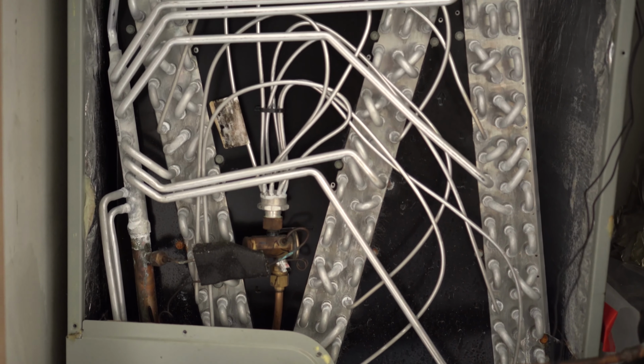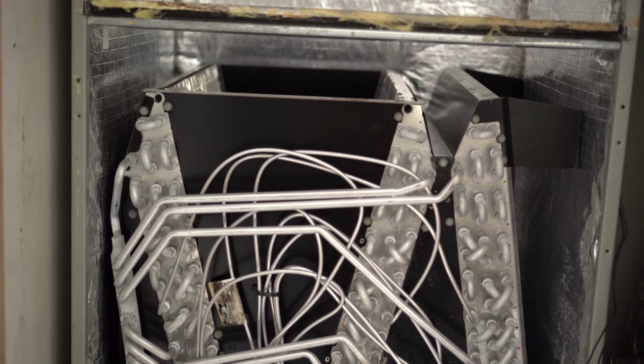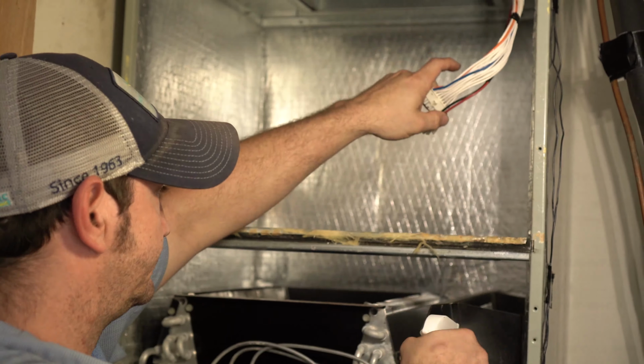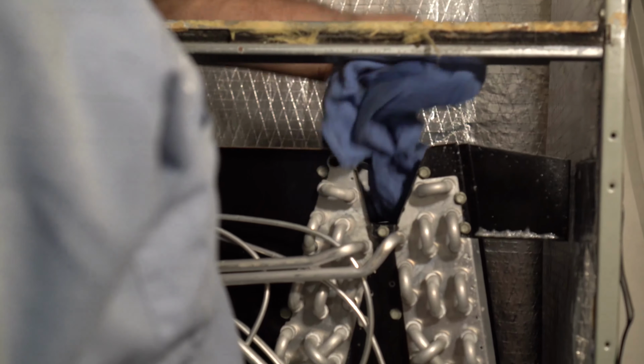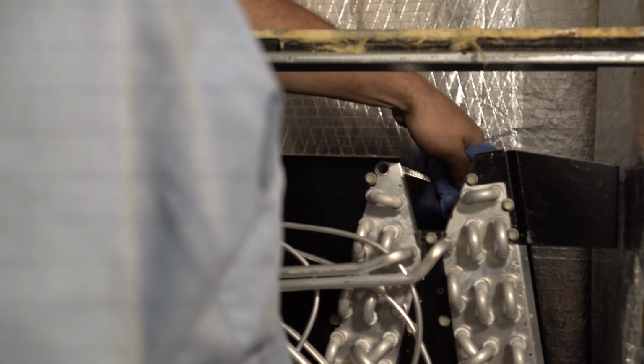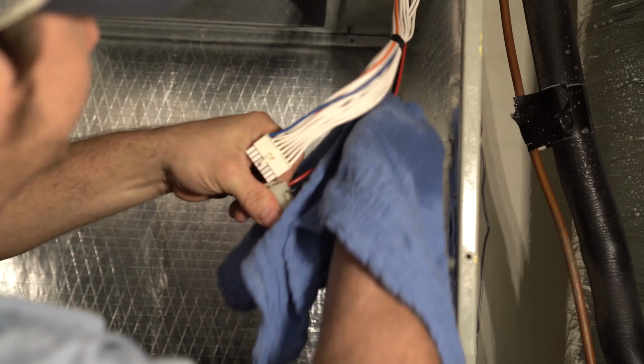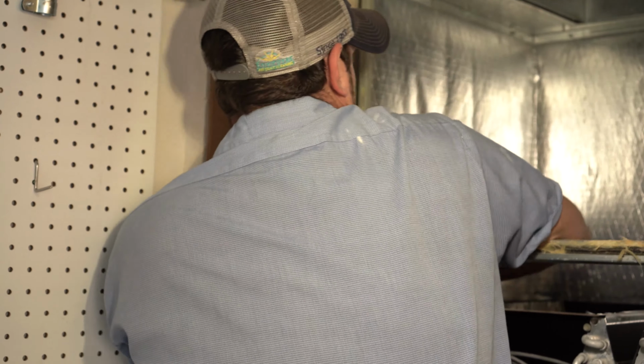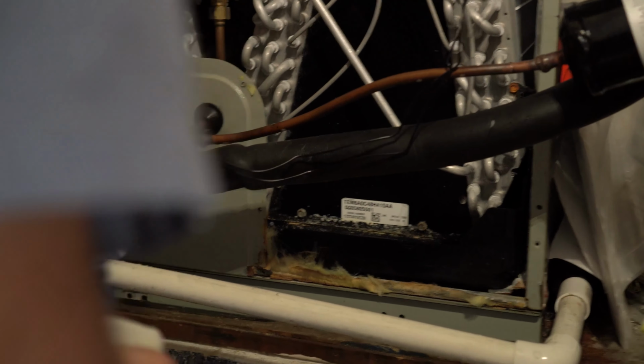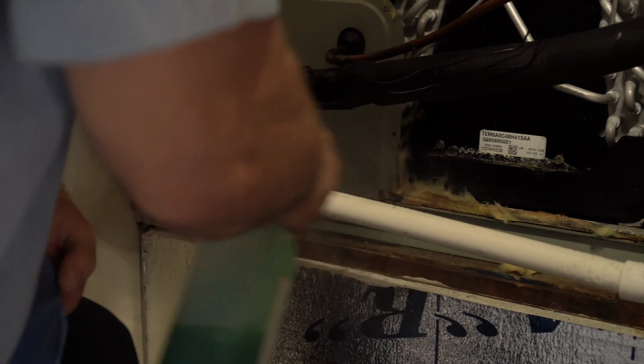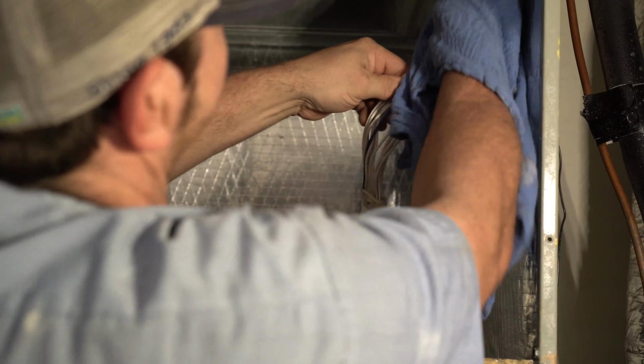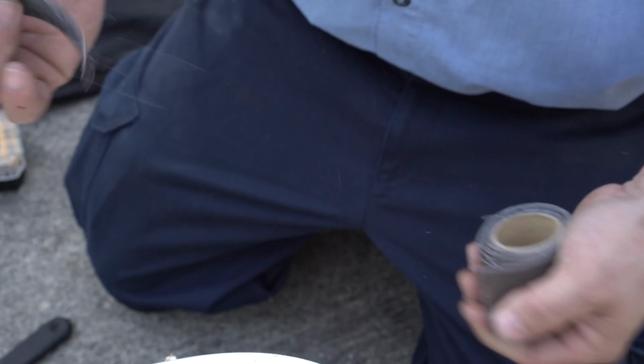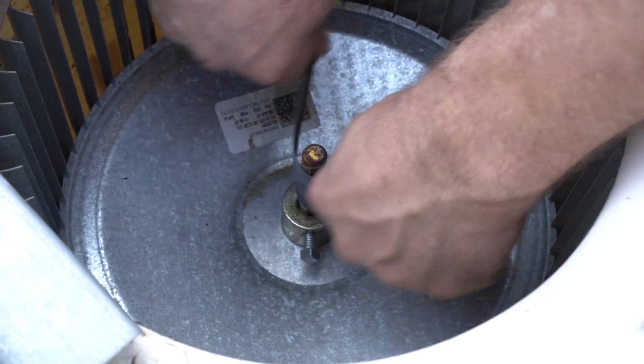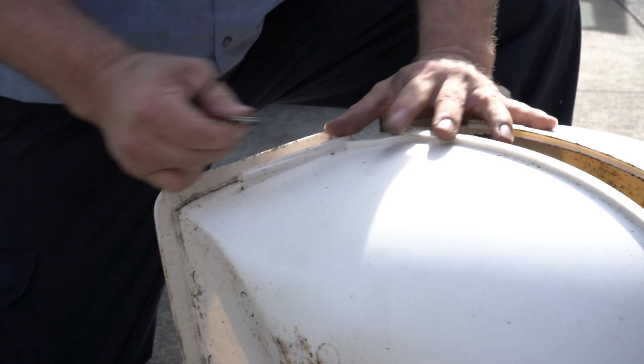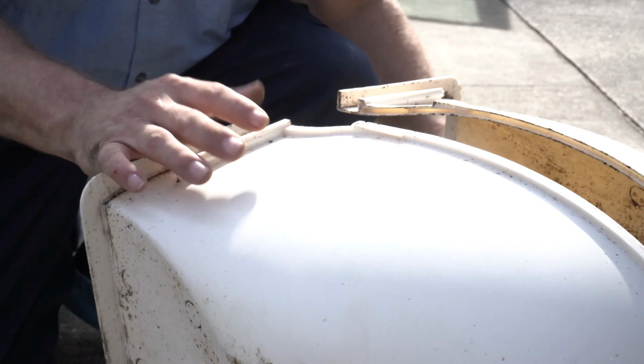Cleaning air handlers can be accomplished by following these important steps. Step 1. Clean the coil in place using an approved chemical like Speed Clean. Step 2. Wipe internal insulation with a rag or sponge dampened with an approved chemical to clean. Step 3. Wipe the exterior of the cabinet using the same process. Step 4. Remove the blower assembly, separating it from the wheel and power wash the wheel and the wheel housing. Be very careful not to get the motor wet during this process.